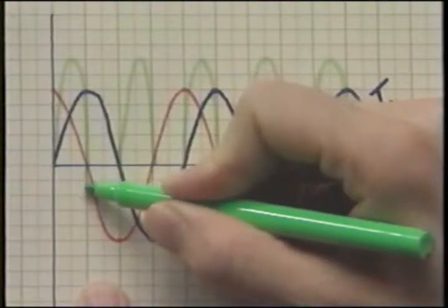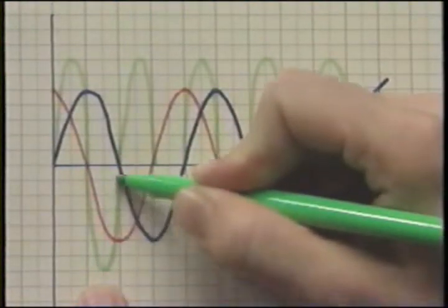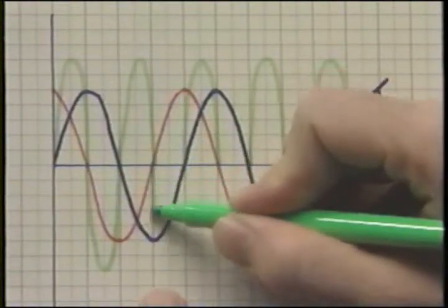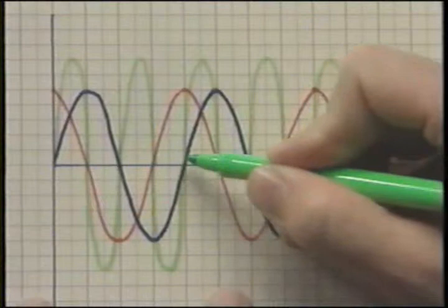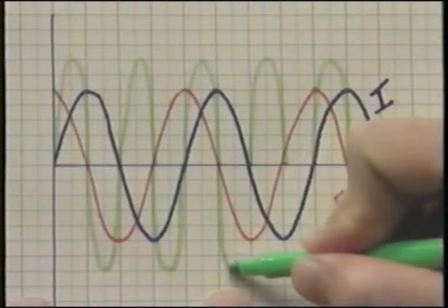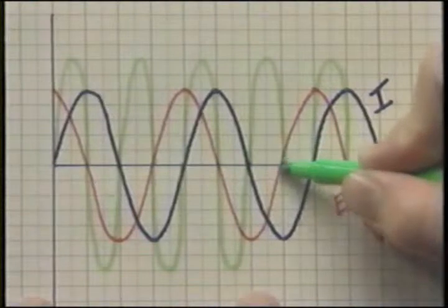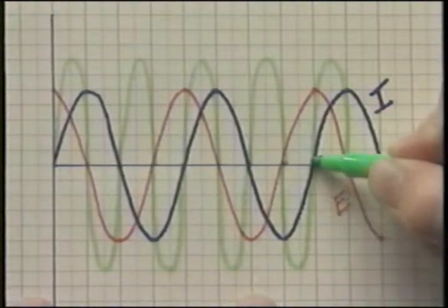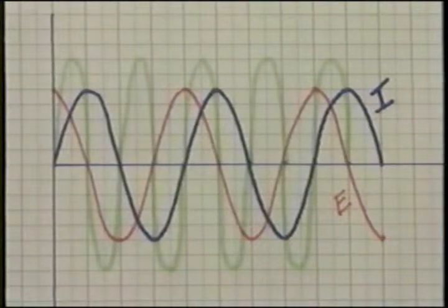However, it's important to realize that multiplying two quantities with unlike signs produces a negative quantity. When a negative current is multiplied by a positive voltage, a negative power curve results. Similarly, when a negative voltage is multiplied by a positive current, you still get a negative power curve. A negative power curve means that power is being returned to the source by the load, rather than being used by the load. A source may be delivering large voltage and line currents, but if the load is purely reactive, no electrical work will be done.